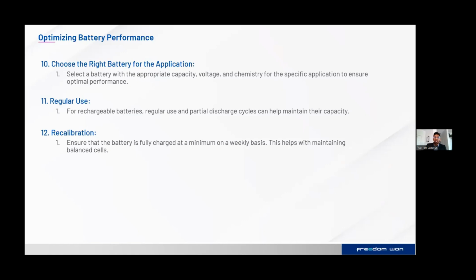Recalibration, which was discussed in depth earlier: for devices with rechargeable batteries, periodic calibration helps the device accurately gauge the battery's capacity. Ensuring the battery is fully charged at least weekly gives a more accurate description of its state of charge.